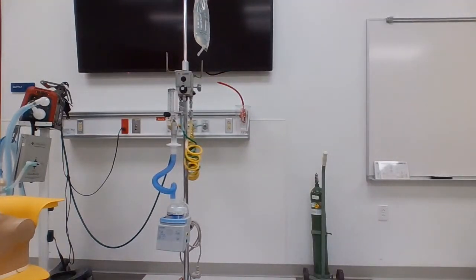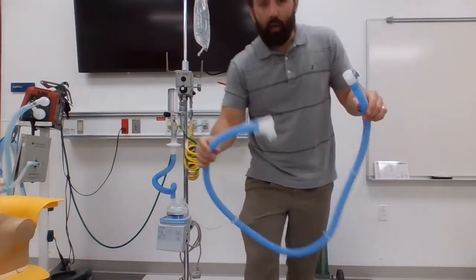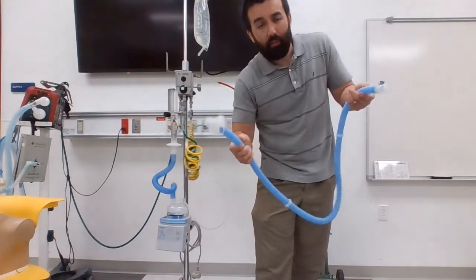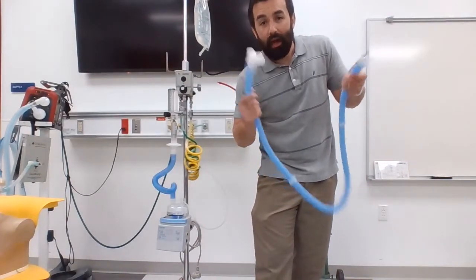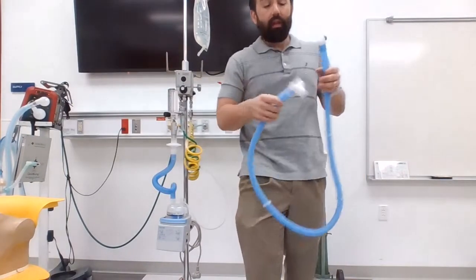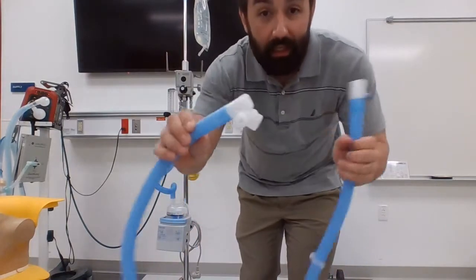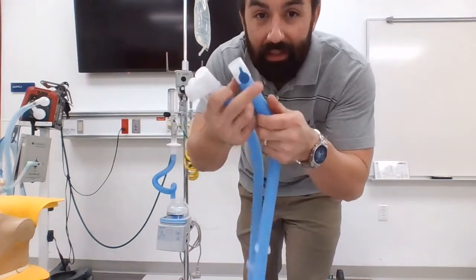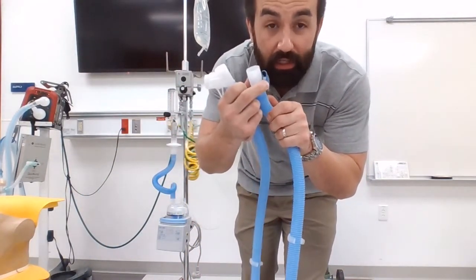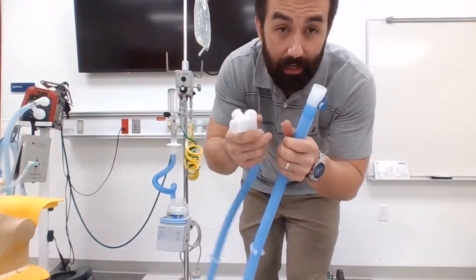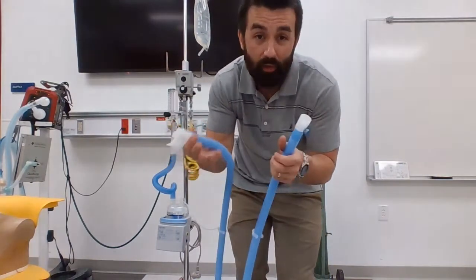Let me show you the other line of this inspiratory heated wire circuit. Optiflow makes circuits that come with this, but I'm stealing mine out of a heated wire circuit for a ventilator. You can see there's a side with this little blue piece that's going to accept what's called a temperature probe, which monitors the temperature of the gas going to the patient.